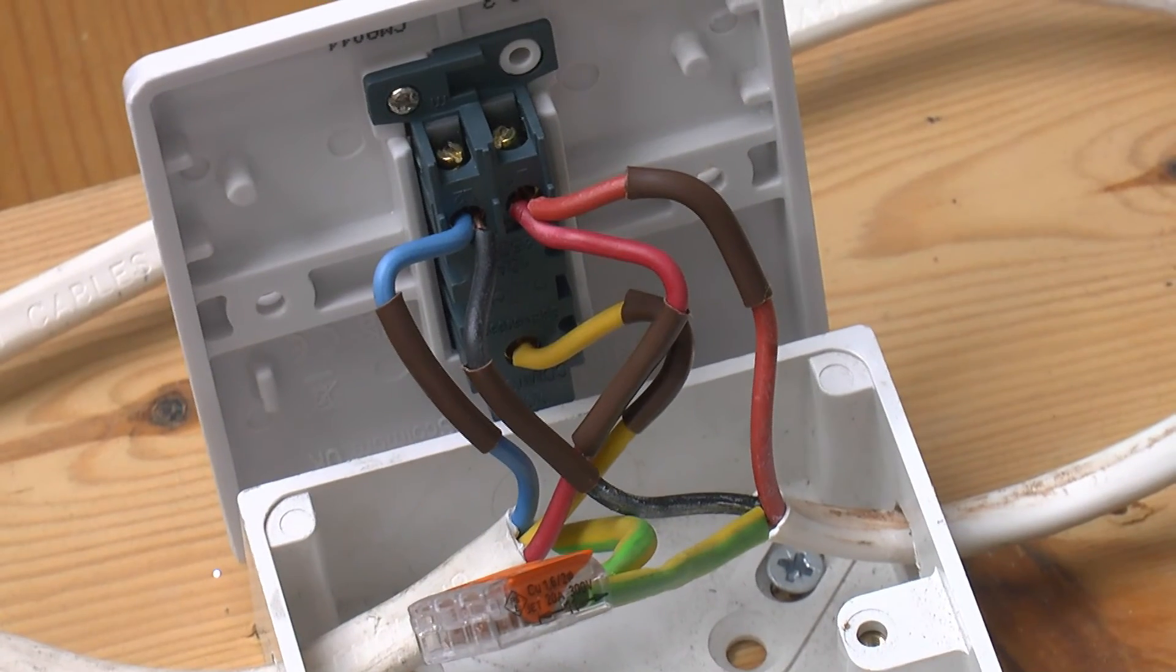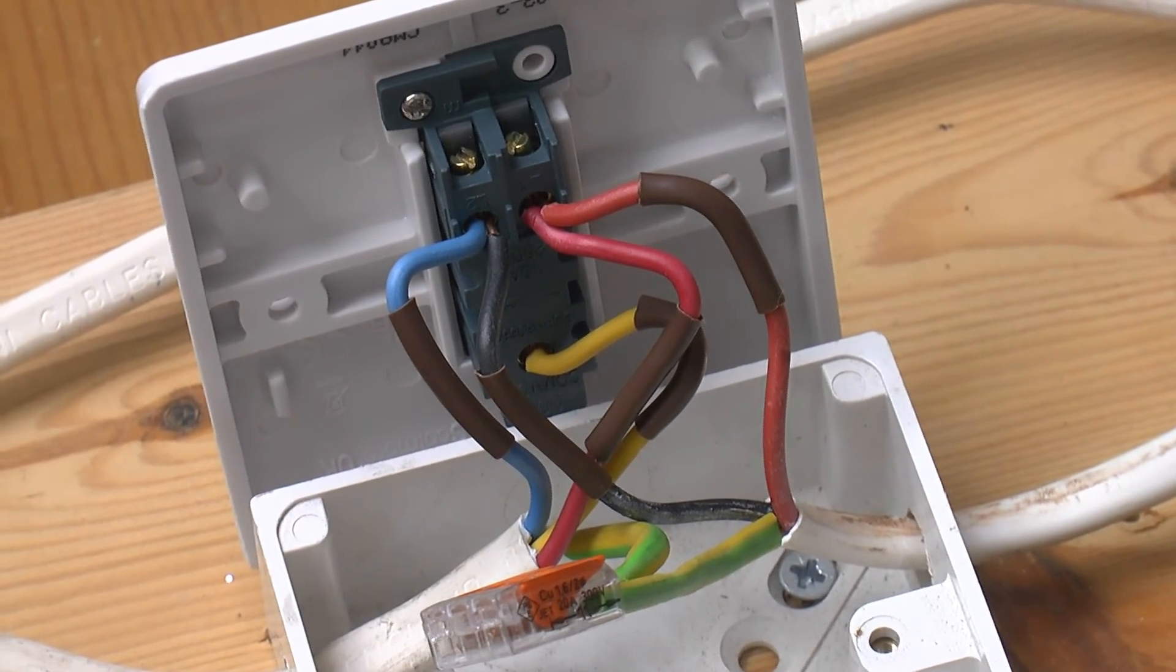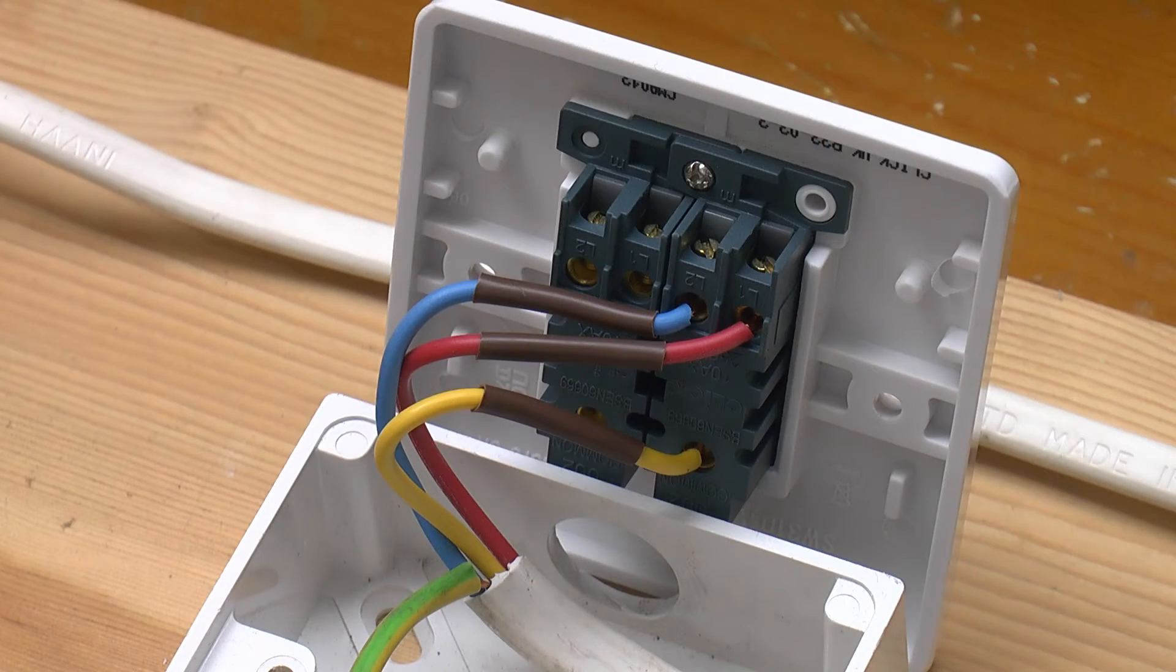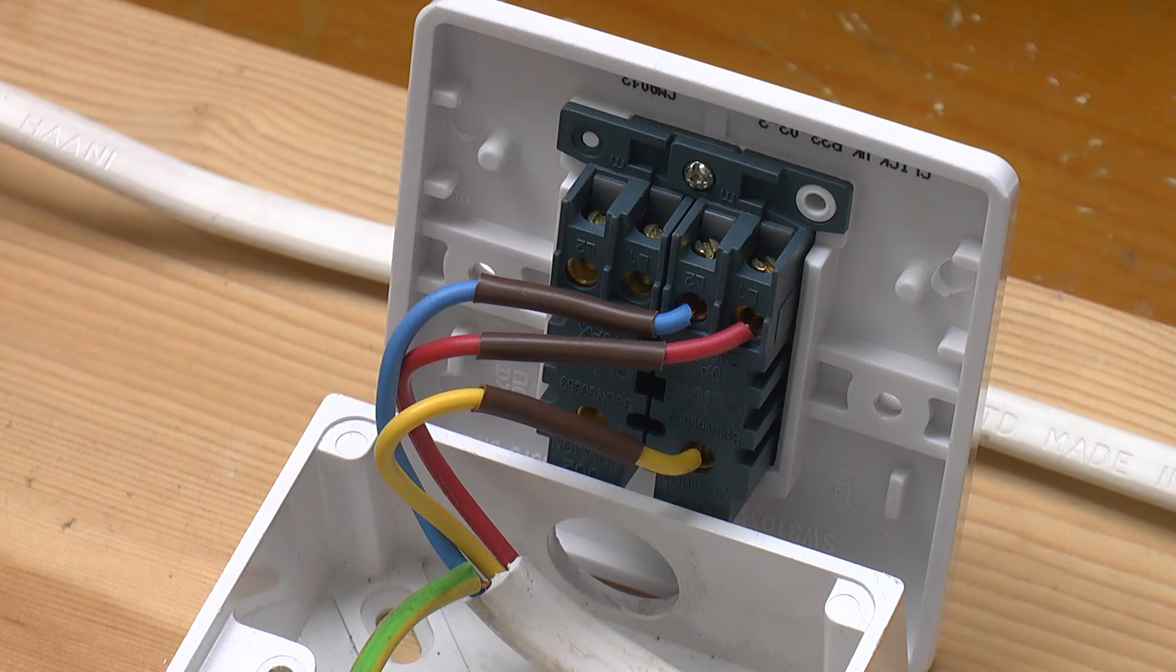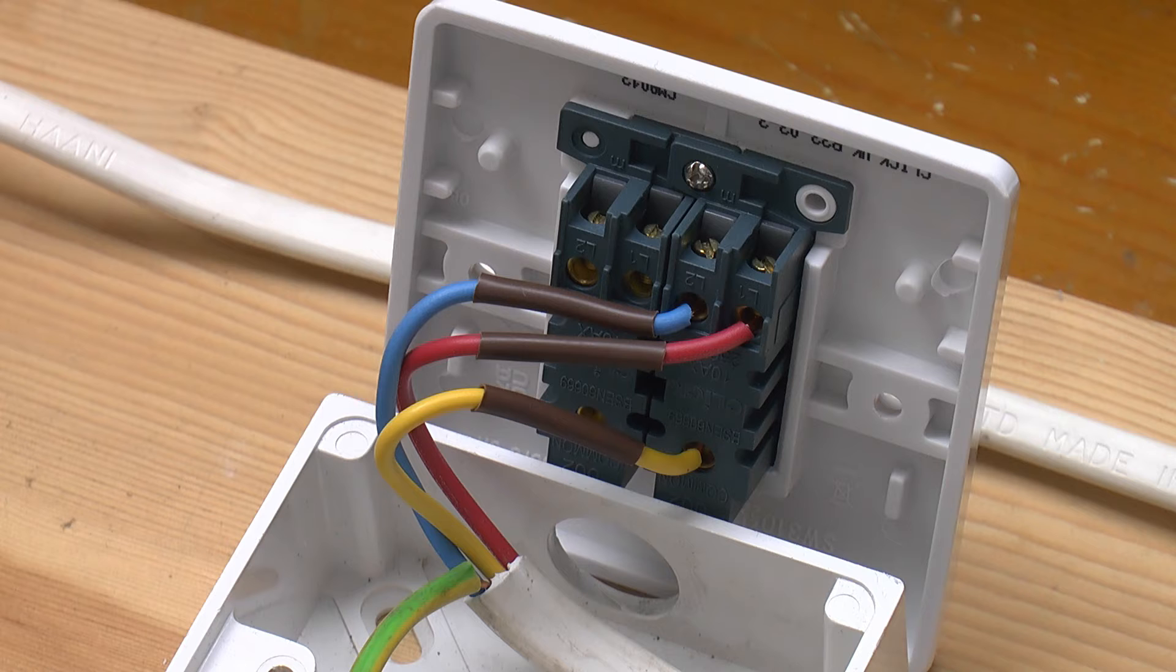The colour coding on the two two-way switches matches like for like, unless, like I said, you want to change whether the light is on or off in the all switches up or all switches down position. This is using the old red, yellow and blue cable, simply because that's what I've got lying around. A new installation would have brown, black and grey instead.